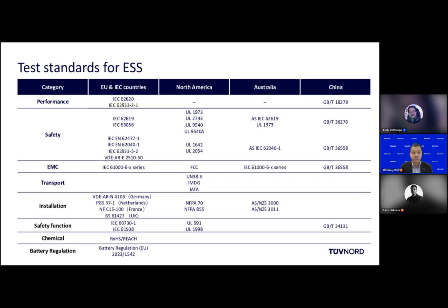62933-5-2 is quite important. It is the safety requirement for the energy storage system, and it covers all aspects from design, from the type approval, and from the factory acceptance test, which is a kind of outgoing test before the product leaves the factory. It also describes how to do evaluations on site as the site acceptance test. And in Germany, we have a special standard, VDE 2510-50, which regulates the safety requirements in Germany.